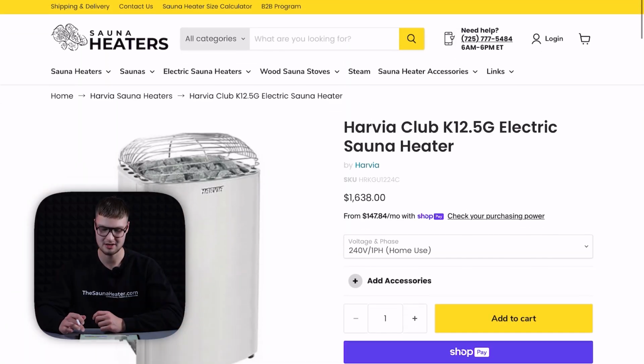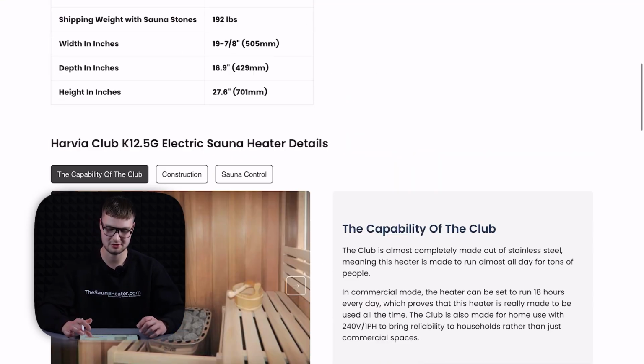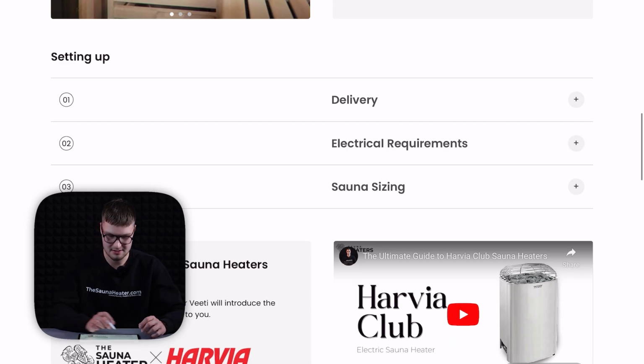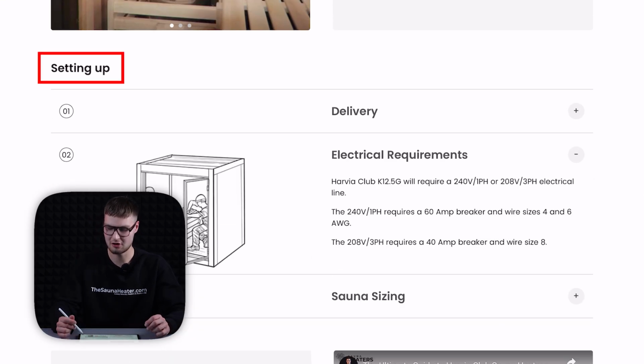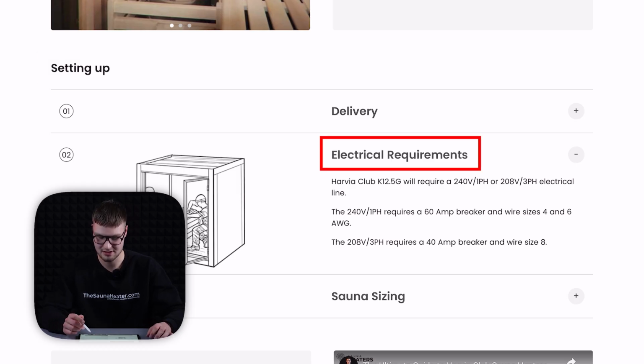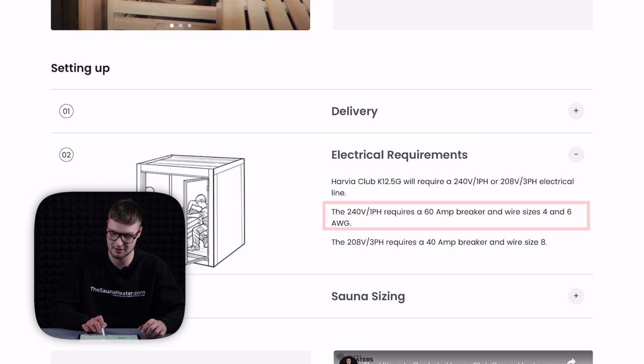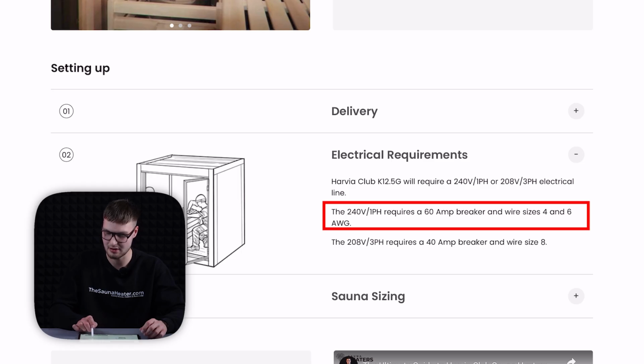Also, on any electric sauna heater page, you can scroll down to the setting up section. When you open the electrical requirements, you'll see everything directly in one place. Here you can see the 240 volt one phase requires a 60 amp breaker and wire sizes of 4 and 6 AWG. That's how you find the electrical information.